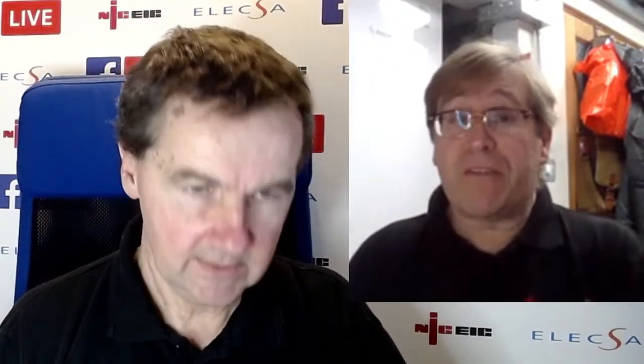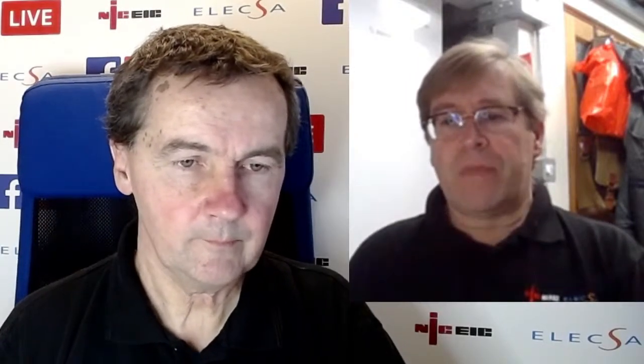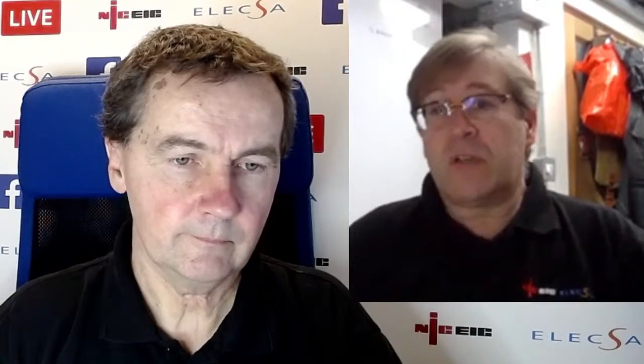What are your thoughts initially on that, Mark? So initially I would say follow the manufacturer, or take account of manufacturer's instructions, regulation 134.1. We generally advise on the helpline to take those into account. But you're quite right saying where there's no chance of an overload situation, when we talk fixed loads like showers and cookers, and generally lots of other stuff like lighting, they're all fixed current using equipment, with no chance of overload.